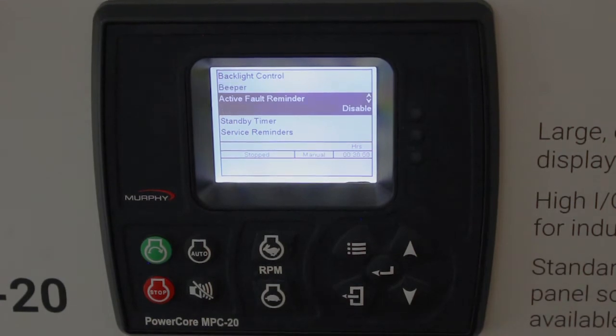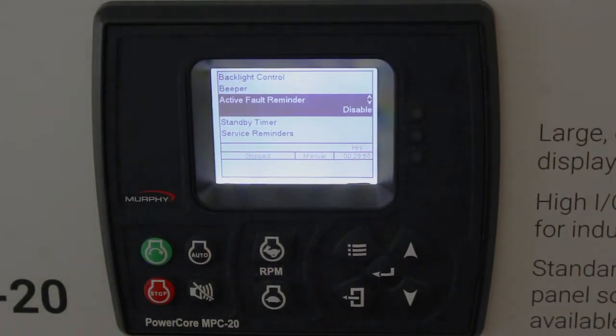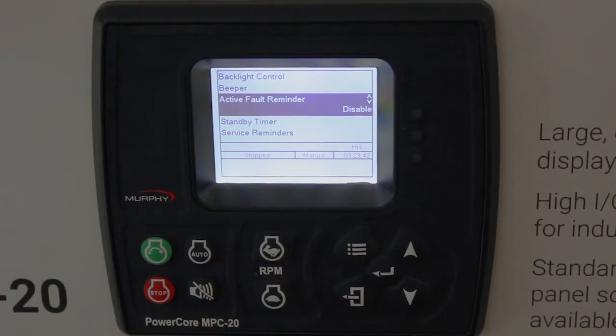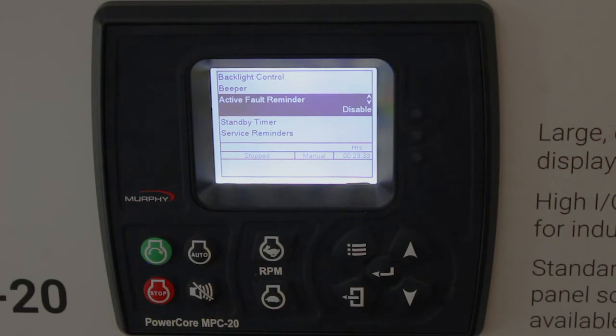Active fault reminder — as long as you don't reset the fault, it will come back. It's about a minute for alarms or warnings, and then every 30 seconds for shutdowns, coming back to tell you that a fault has occurred. It defaults to disabled, but if you want to be reminded that a fault occurred and you haven't reset anything yet, you can choose enable for that.